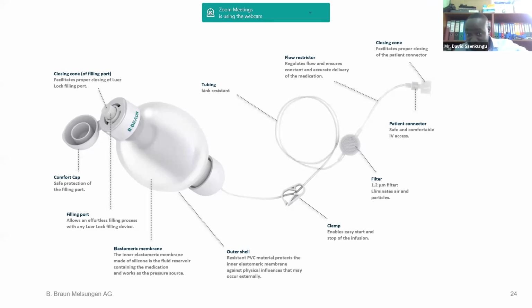We have the clamp, basically to start or stop the infusion. Then we have the tubing, which is kink resistant. Then we have a filter, which is both a particulate and air filter. It's about a 1.2 micron microfilter for both air and particulate. Then we have the flow restrictor. This regulates the flow, which ensures constant and accurate delivery of the medication. We have the patient connector for safe and comfortable access, and then the closing cone for proper closing of the patient connection.